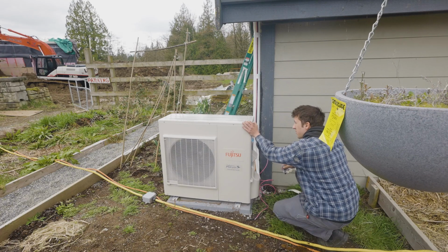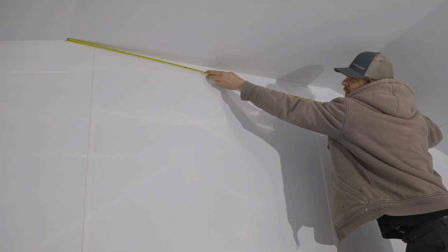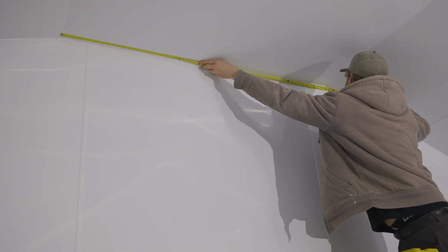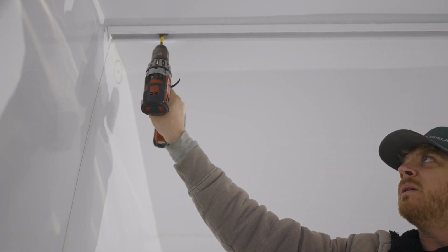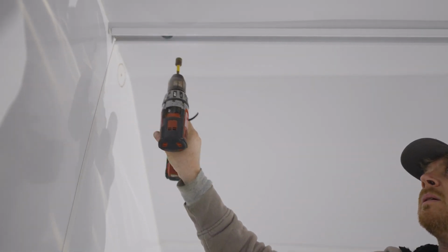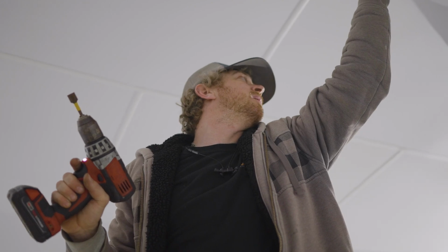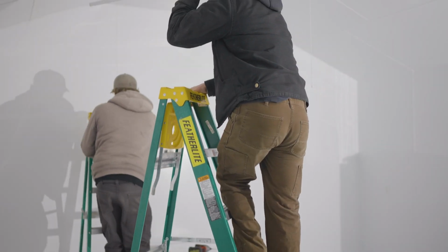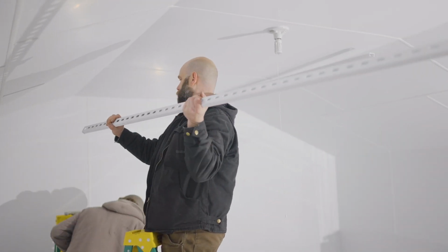We get the layout of the room. Every room's different. We can have the air handler fan coil outside the room. The return air can be ducted at a 5-foot level, pulling that heat from the plant and the light, blowing the supply air down on an 8 and 4 o'clock position, down along the canopy. So your cool air will naturally fall, your hot air will naturally rise.